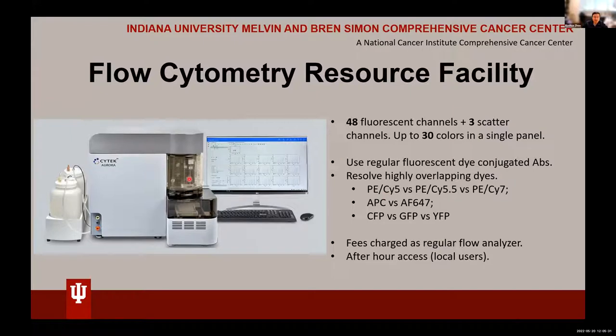Sometimes when you're doing an experiment with only five or six colors and you want to add another antibody, you look in your fridge and find you have PE-Cy5 and the antibody you want to add is PE-Cy5.5 or PE-Cy7. In a regular flow machine it's difficult to accommodate both PE-Cy5 and PE-Cy5.5 because the spectra heavily overlap. But with the Cytek Aurora you can just add that antibody. Similarly, APC versus Alexa Fluor 647 is difficult to run together on a regular machine. I had trouble doing lineage tracing for regulatory T cells labeled with GFP and YFP — difficult to resolve on a regular machine, but easy on the Aurora.